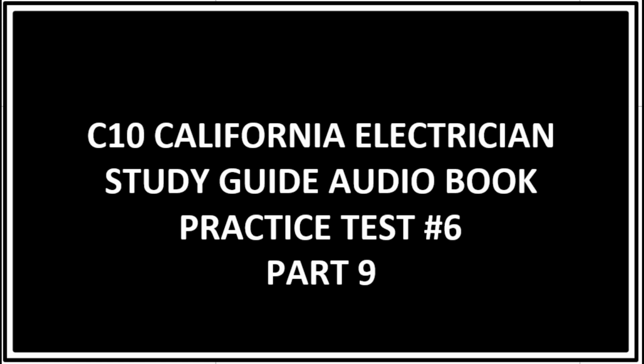Question 104. What is the minimum working distance in front of a main service panel? 36 inches. A main service panel requires 36 inches minimum working space.